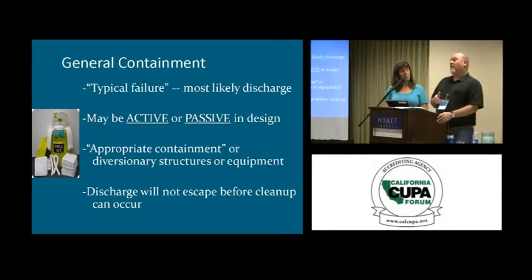And part of the responsibilities for developing, certifying, and implementing an SPCC plan lie with the owner-operator, first and foremost. Then, if they are 10,001 gallons plus, there's a professional engineer certification requirement. For those that are 10,000 and below, it's a self-certification as qualified facilities. But the responsibility lies with the owner-operator to make a determination as to what is the most likely discharge, and if there's a professional engineer requirement, they would assist or make those calculations.